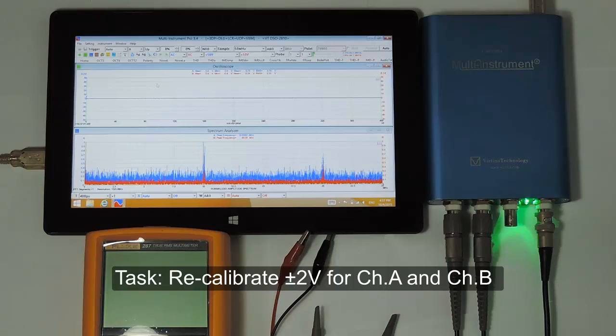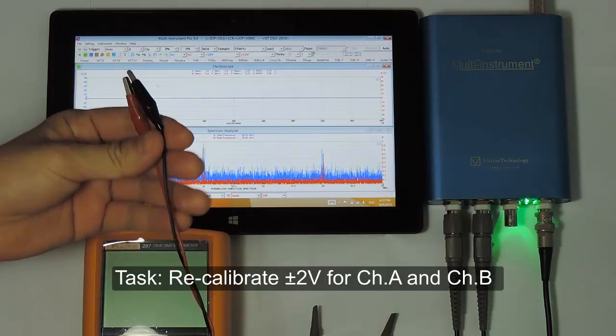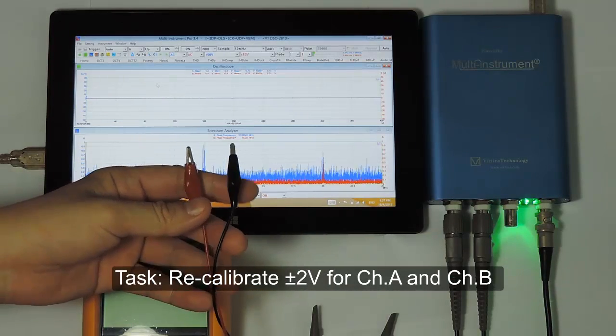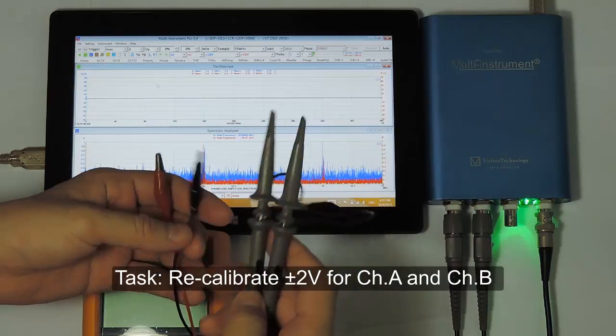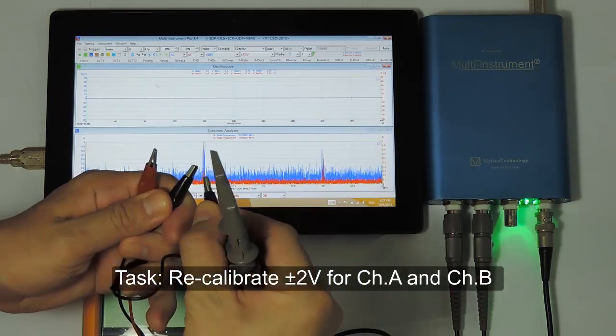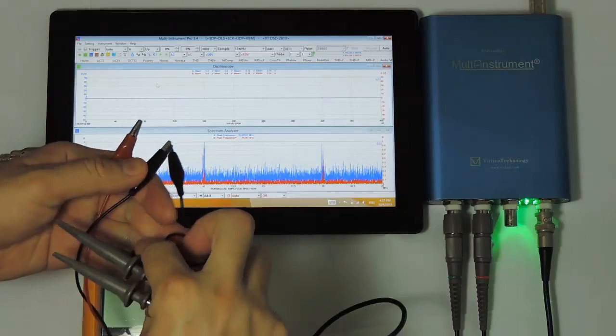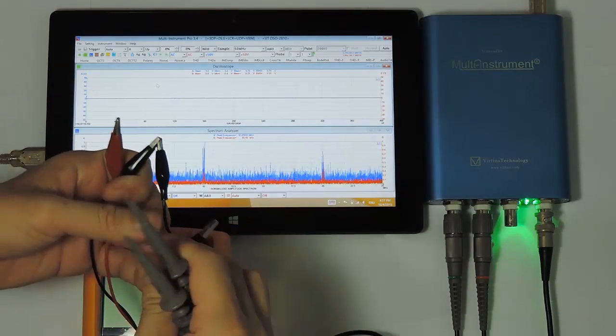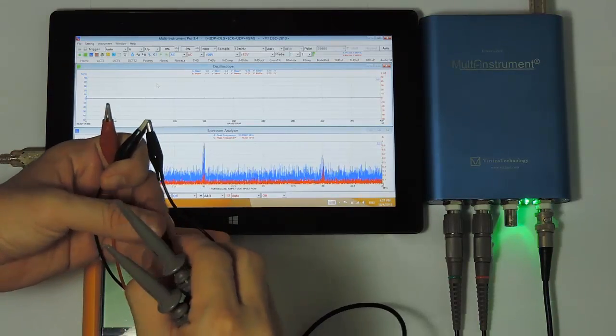Here we are going to show you how to conduct recalibration for the voltage measuring range of plus minus 2 volts for both channel A and channel B. Let's connect the output of the signal generator to the input of channel A and channel B first.